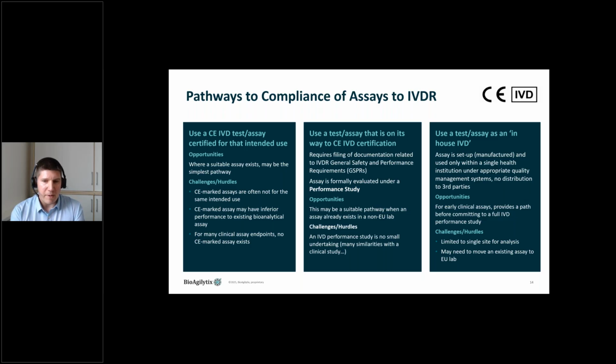Still the gold standard pathway, also the way to CE marking, if you already have an assay in place and you've built an assay under design control that fulfills most of the analytical criteria, but still lacks the performance data, would be running a performance study for the device. So this is an opportunity if there has been substantial work already done, also for example, in a non-EU lab, but it comes with some challenges as well, as an IVD performance study is not really a small undertaking.